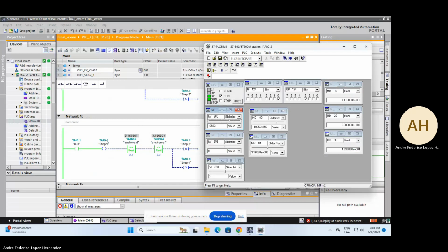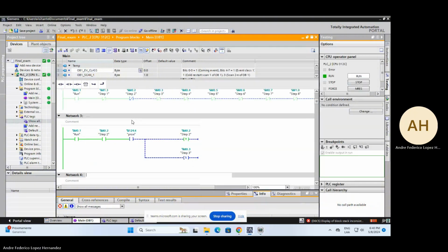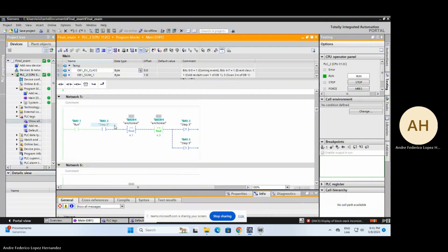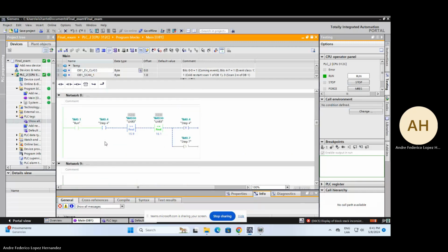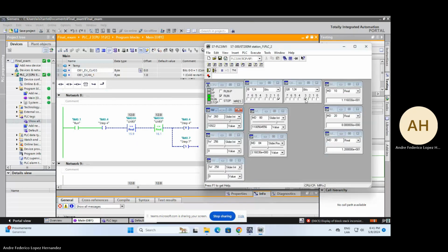As soon as an eject cylinder control is turned on, the UX3 reading is invalid because the part is being moved off the conveyor. The actual distances are measured by the ultrasonic transducers that are connected to analog input channels, and the device values are converted into units of inches and stored in internal memory locations as real numbers. Then the ladder logic program is divided into smaller steps and transitions that are linked together in a logical sequence.